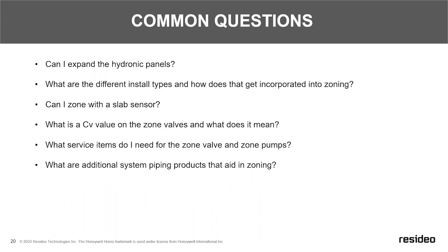So when we're looking at pressures in a hydronic system, we typically look at feet of head, not PSI. So there's another formula you can ingrain in memory: 1 PSI equals 2.31 feet of head. So essentially, if you're driving 3.5 gallons a minute through a zone valve that shows a CV of 3.5, you're going to get 2.3 feet of head resistance through the valve.